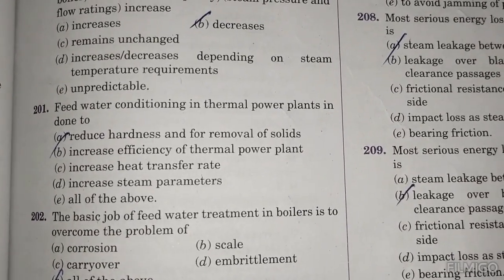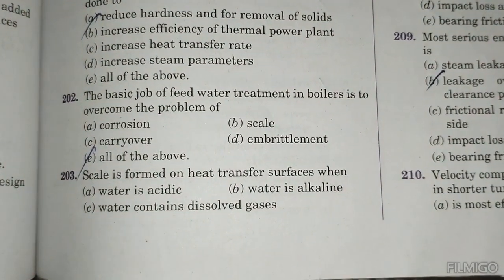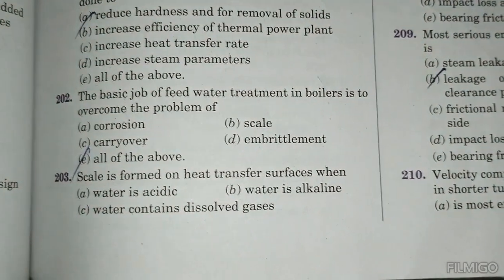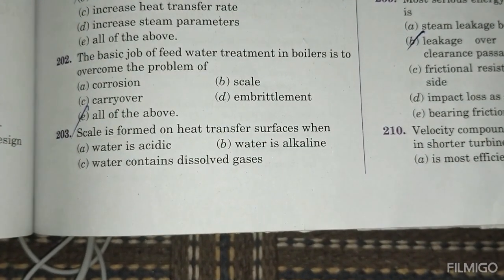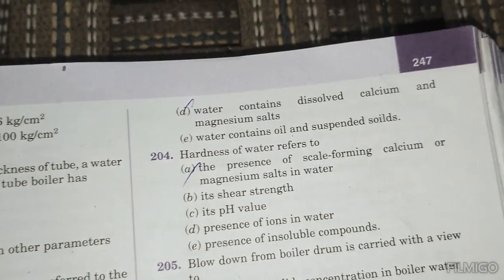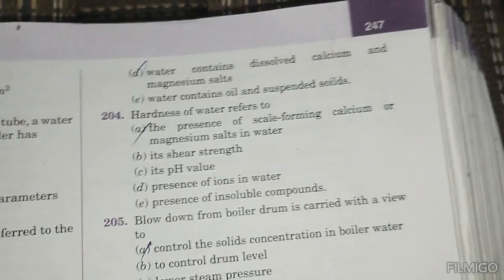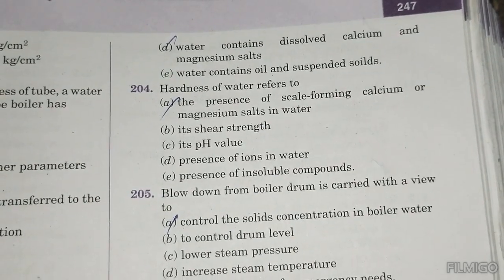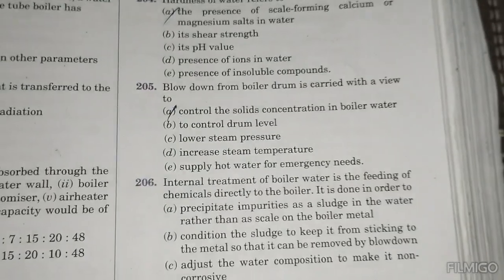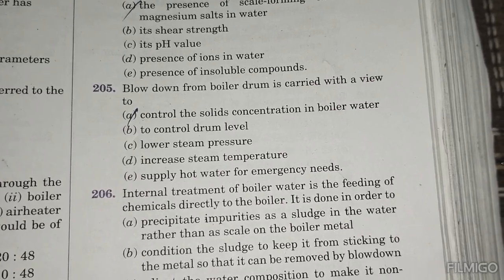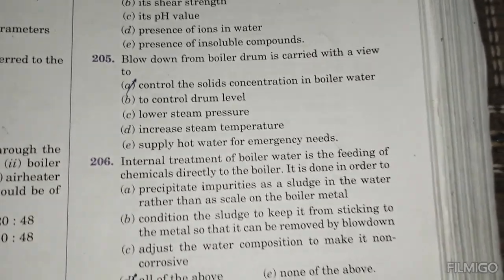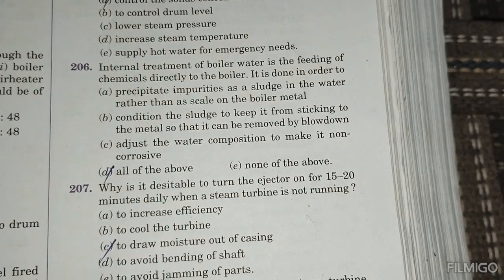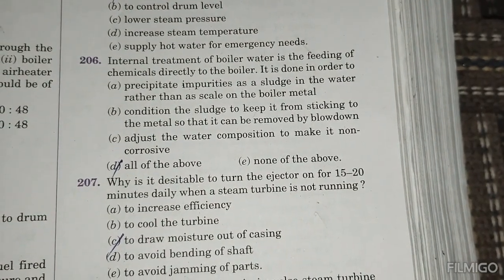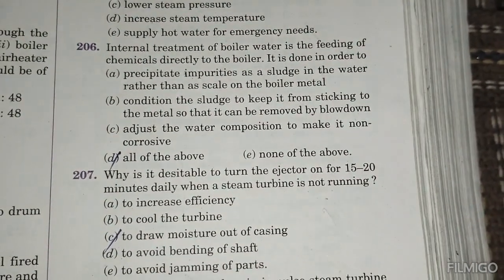Feed water conditioning in a thermal power plant is done to reduce the hardness and remove solids. The basic job of feed water treatment in a boiler is to overcome the problem of all of the above. Scale is formed on the heat transfer surface when water contains dissolved calcium and magnesium salts. Hardness of water refers to the presence of scale forming calcium and magnesium salts in water. Blowdown from the boiler drum is carried out with a view to control the solid concentration in boiler water. Internal treatment of boiler water is feeding of chemicals directly to the boiler, done in order to achieve all of the above.